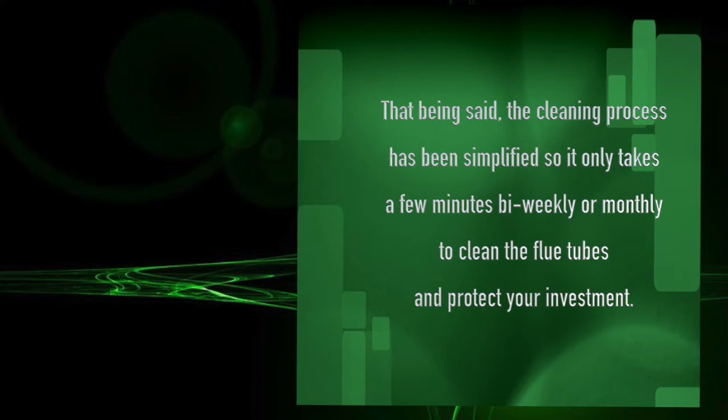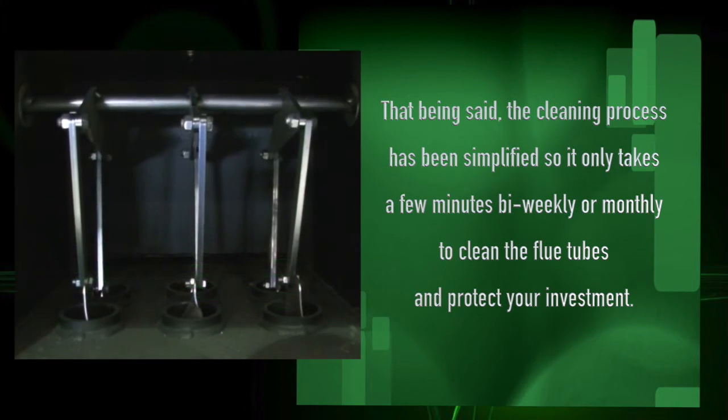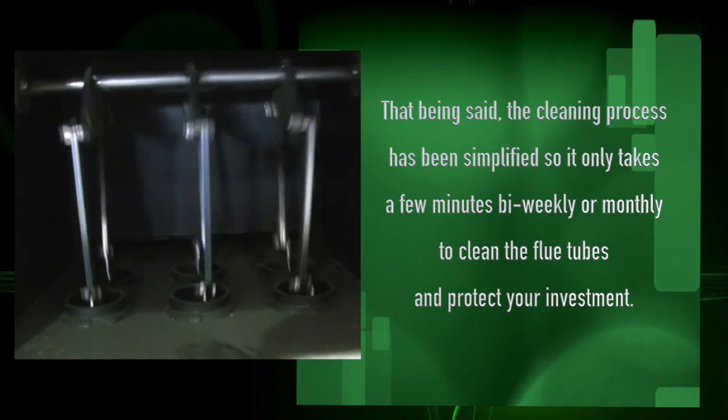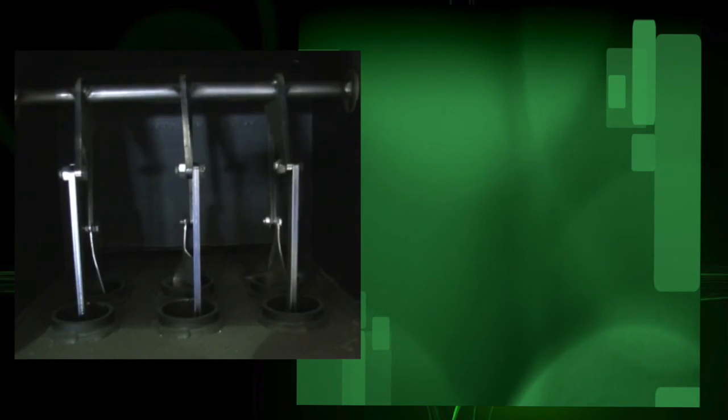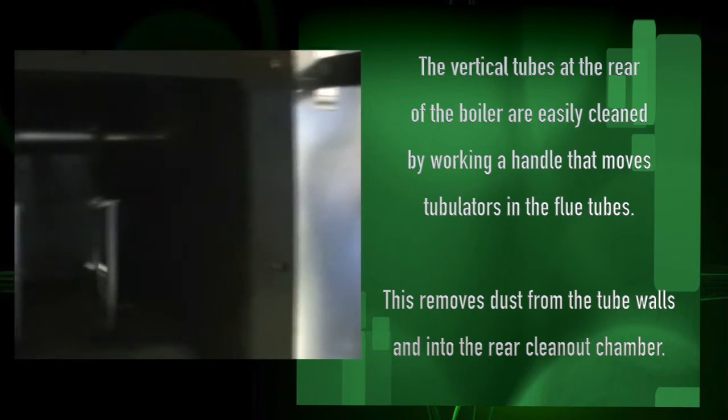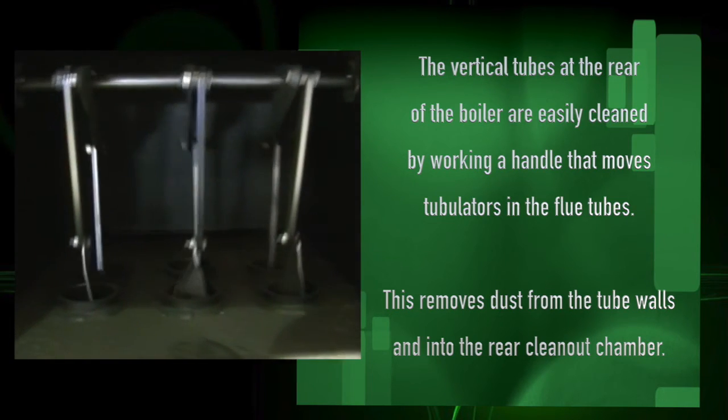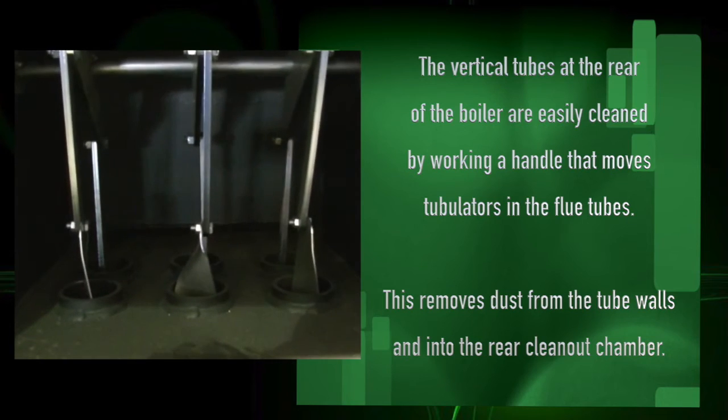That being said, the cleaning process has been simplified so that it only takes a few minutes, bi-weekly or monthly, to clean the flue tubes and protect your investment. The vertical tubes at the rear of the boiler are easily cleaned by working a handle that moves the tubulators in the flue tubes.